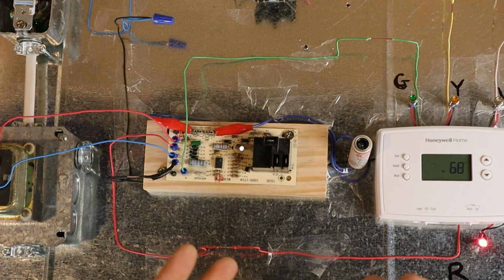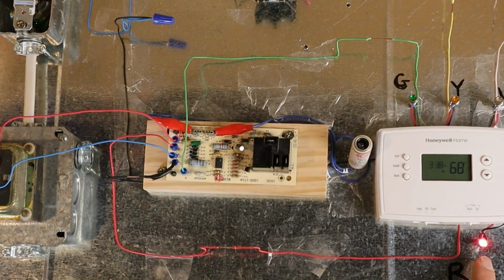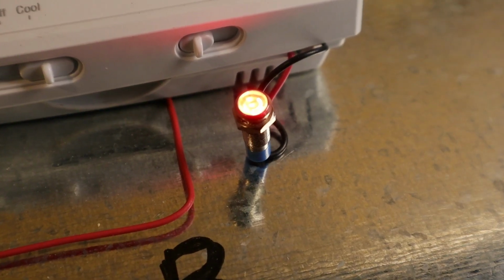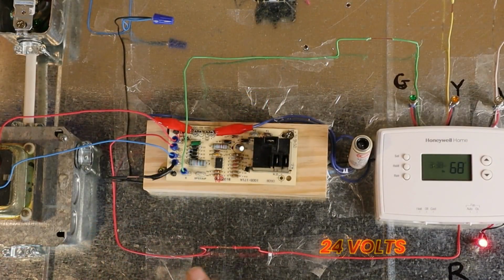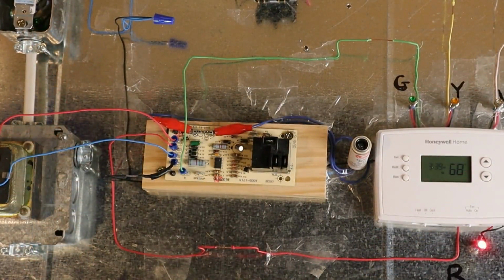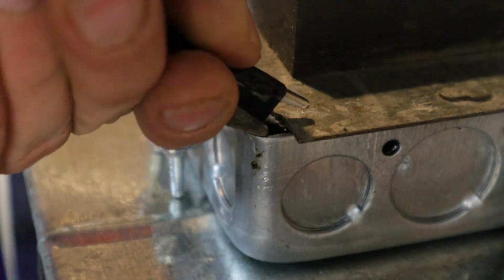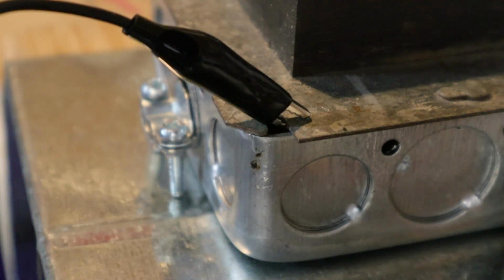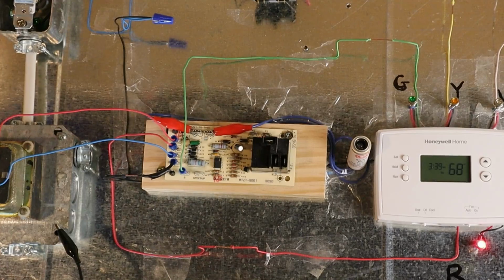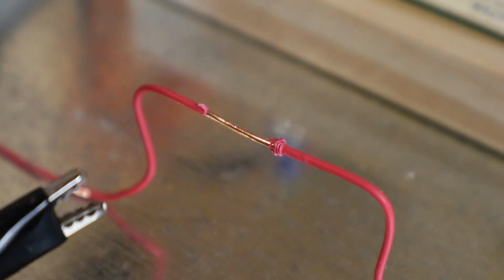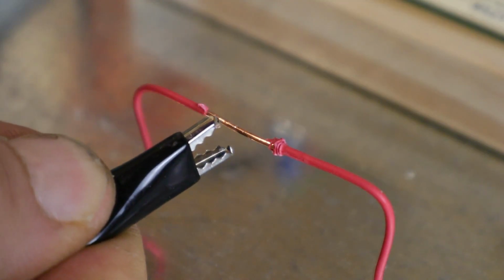What I have here is a model control circuit that's pretty typical in heating and cooling systems, and you can see I have a little red indicator light here that indicates that I have 24 volts through this wire here. Now right here I have a little bare spot of copper. Now what I'm going to do is take this alligator clip and clip it onto the metal box here, which could be the chassis of the unit or ductwork, and I'm going to take the other end and clip it right on that bare piece of copper. Now what do you think is going to happen?